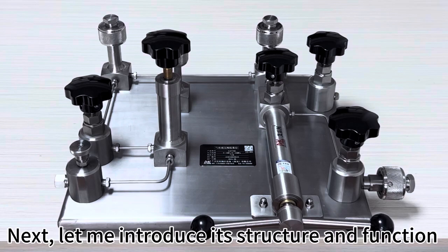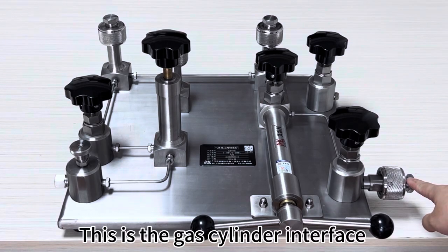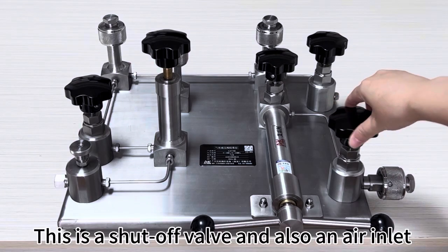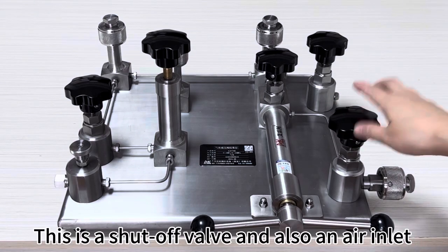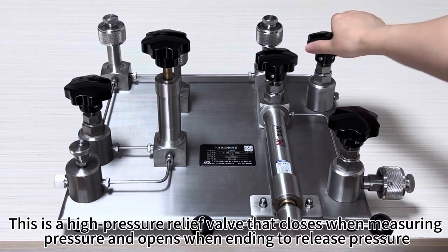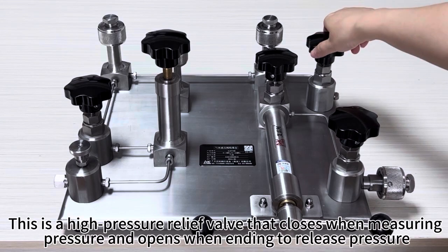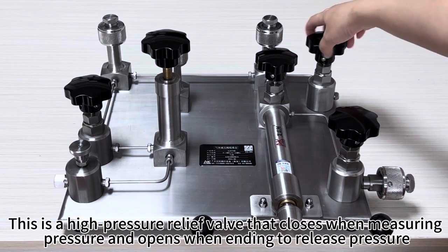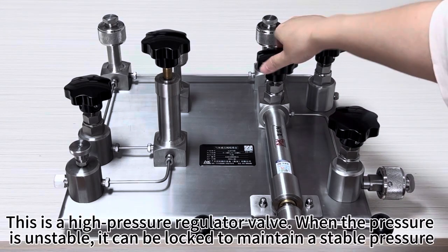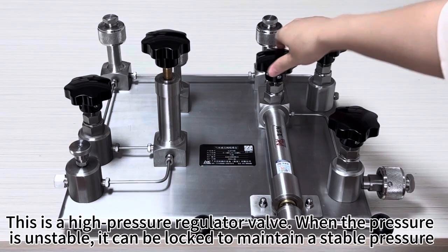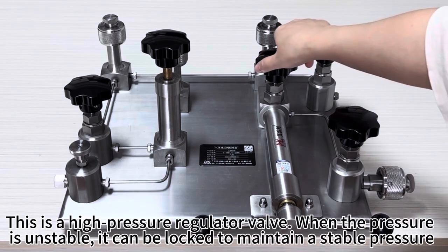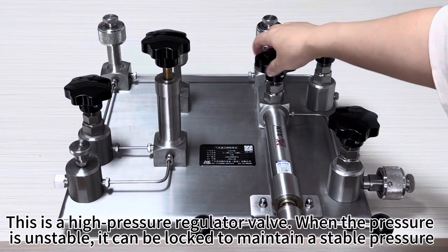Next, let me introduce its structure and function. This is the gas cylinder interface. This is a shut-off valve and also an air inlet. This is a high-pressure relief valve that closes when measuring pressure and opens when ending to release pressure. This is a high-pressure regulator valve. When the pressure is unstable, it can be locked to maintain a stable pressure.